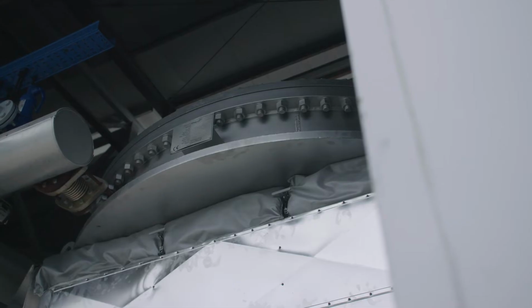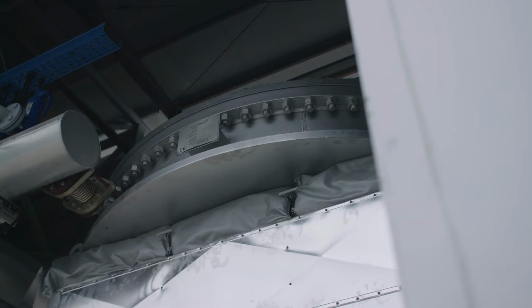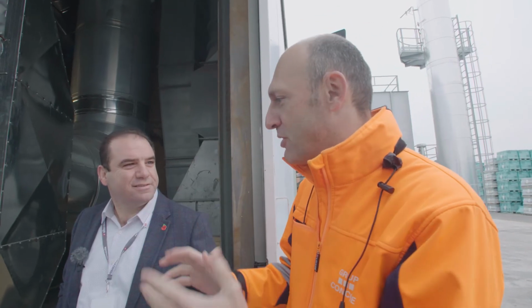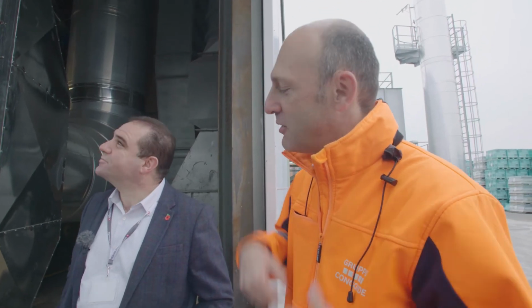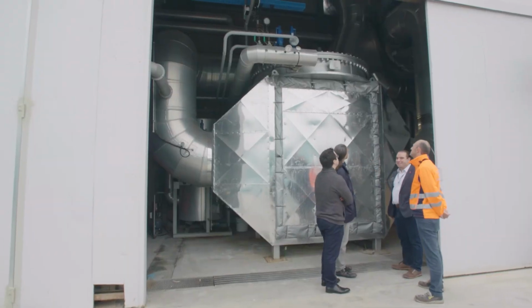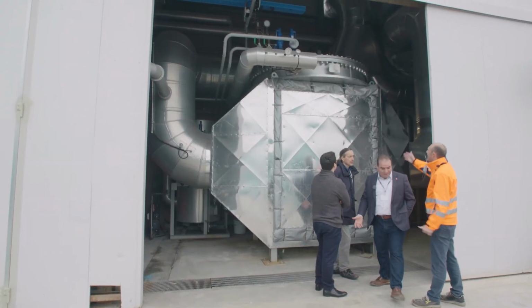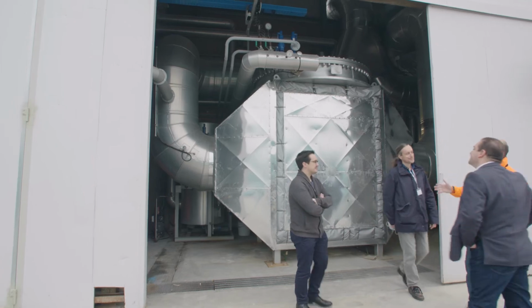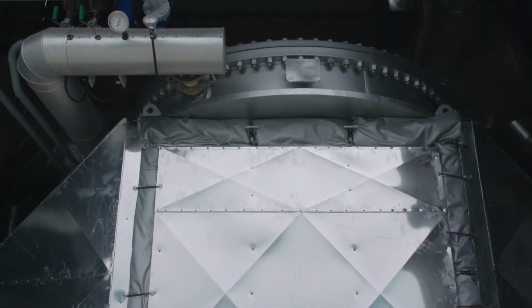The fully functional prototype recovers waste heat from the furnace at a temperature of around 245 degrees Celsius. This waste heat powers a pressurized water cycle from 115 to 155 degrees Celsius at the top of the unit. The hot water cycle is then used to heat the spray dryer at the beginning of the production process. The inventor of the Etekina heat pipe heat exchanger technology is Professor Hussam Jouhara from Brunel University, London.